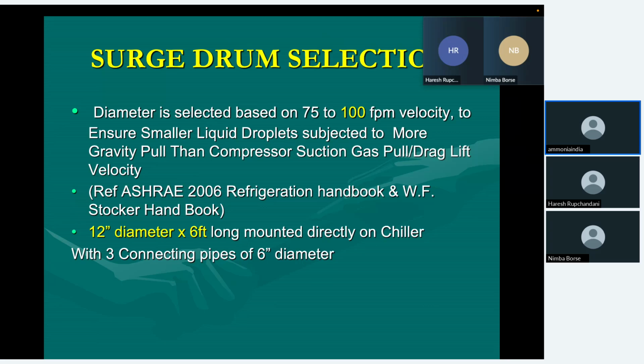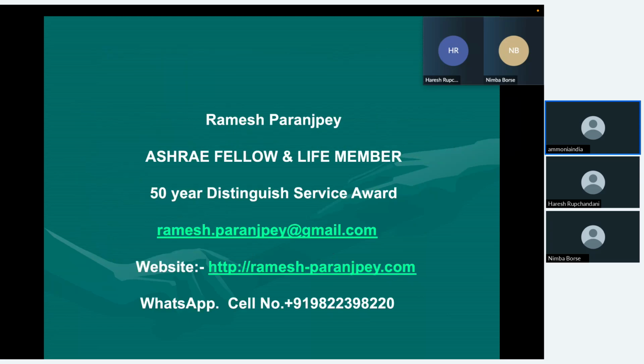This is for the surge drum velocity. So the surge drum mounted on the top of that is 12-inch diameter, 6 feet long, directly mounted on the chiller, and the pipelines connecting to this are selected on the basis of 75 to 100 fpm velocity. So with 3 connections, pipes of 6-inch diameter are used between chiller and the surge drum. This is the chiller design.